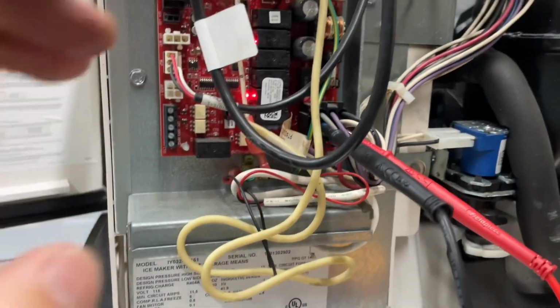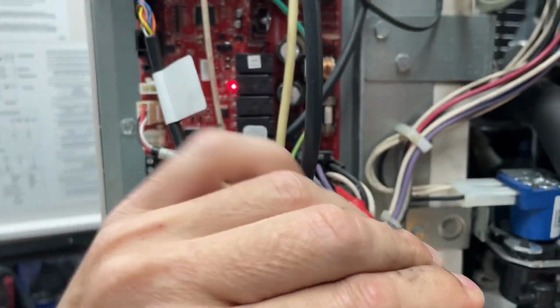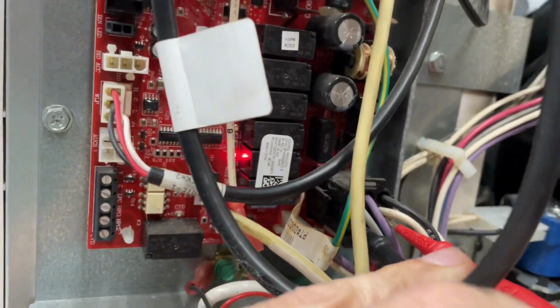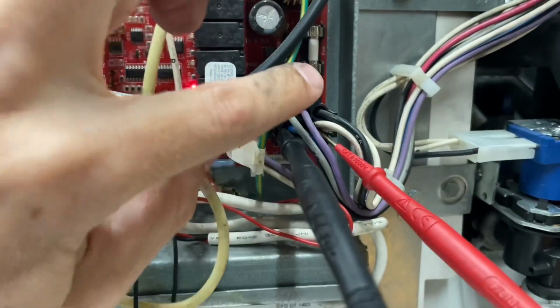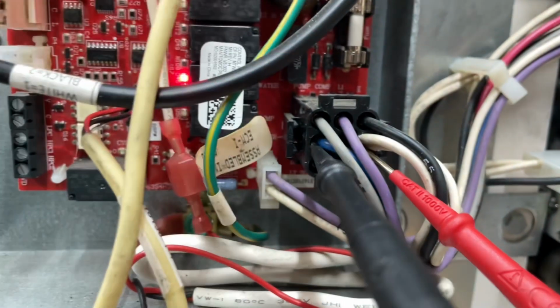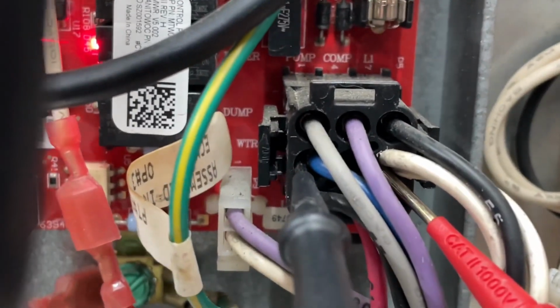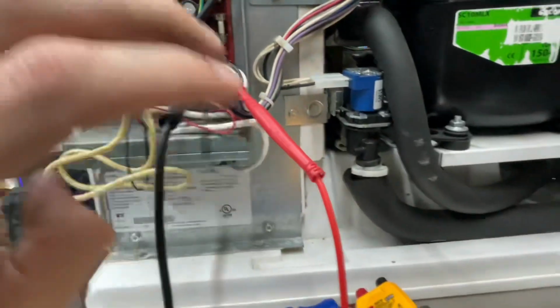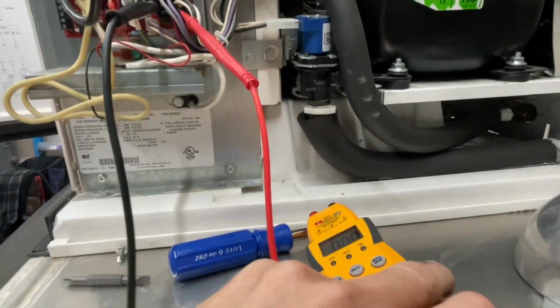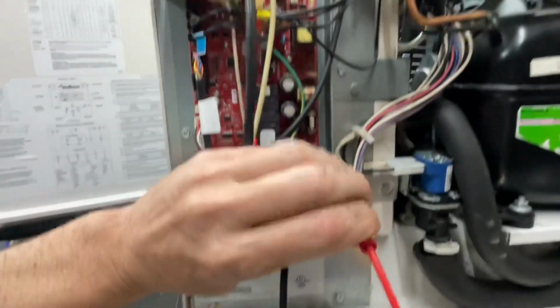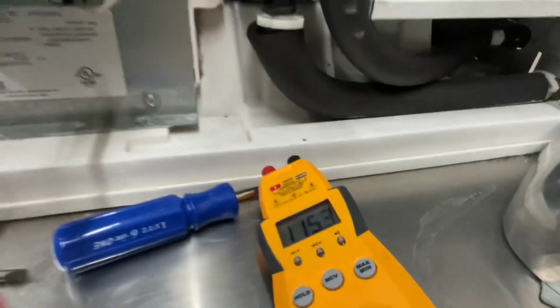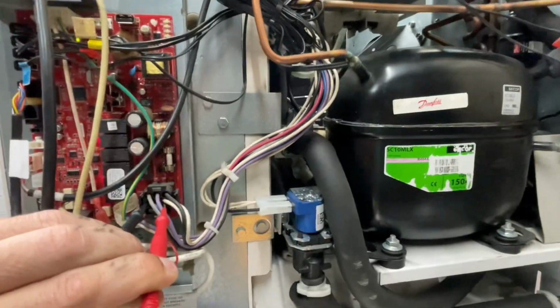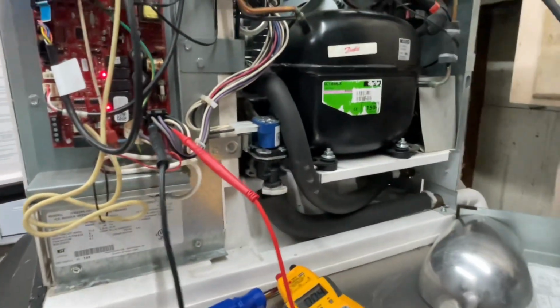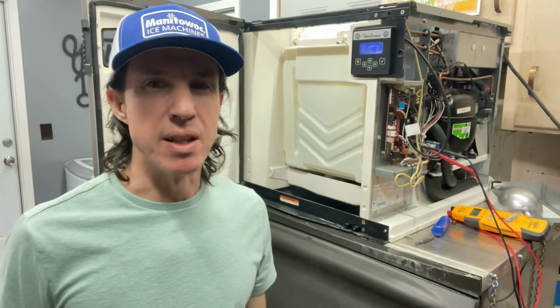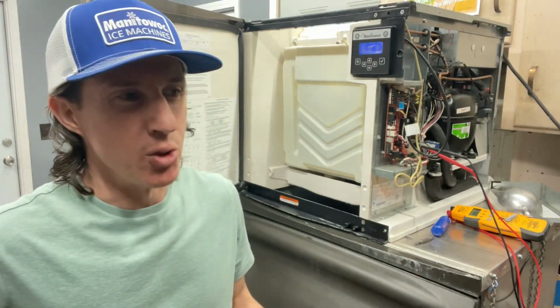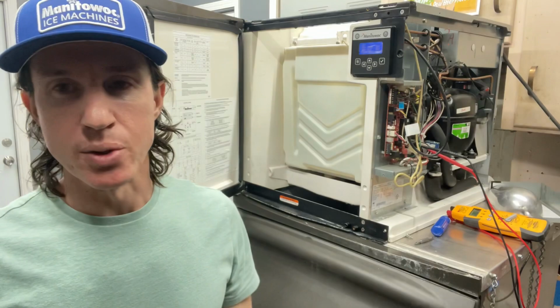You can't really see it. But what we're gonna do is we're gonna measure between our L2 and our blue wire, which is also labeled water, which is, get a good shot of that for you, labeled water right there. So turn this on and push these in. What are we getting? 115. That water valve back there should be energized, but it's not. This has got to be the simplest thing to do. Do it once, do it twice. You'll be able to do it every time.